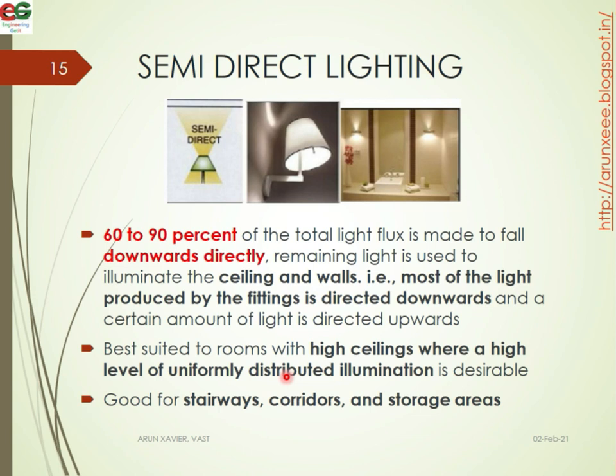In semi-direct lighting, 60 to 90% of the total light is directed downwards directly onto the work plane, and a certain amount of light is directed upwards. This type is best suited for rooms with higher ceilings, providing a high level of uniformly distributed illumination.